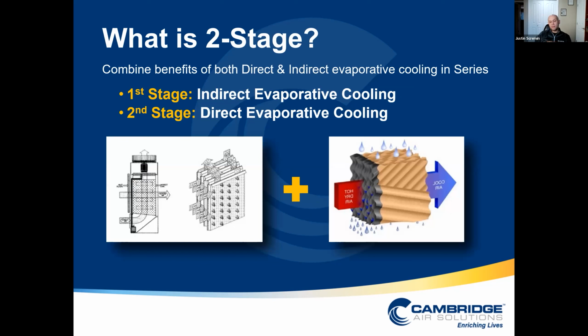With two-stage evaporative cooling, the first stage is going to be different, but the second stage is exactly the same — that's the direct evaporative cooling. We get a bunch of capacity out of that, but we have to modulate it with a humidistat in the space. Instead, we can use an indirect section as opposed to, or in addition to, the direct section.